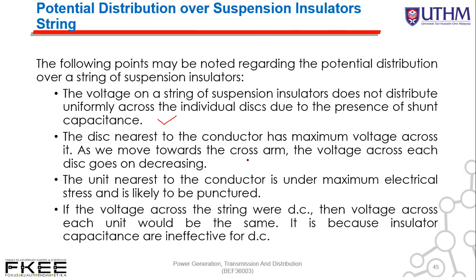As we move toward the cross arm, daripada bawah, kalau katakanlah ni konduktor, kemudian naik ke atas, kita ada 3 disc, C, C dan C. So voltage yang paling bawah, dekat konduktor, paling tinggi, kemudian naik ke atas, voltage dia makin berkurang. Okay, the unit nearest to the conductor is under maximum electrical stress and is likely to be punctured. If the voltage across the string were DC, the voltage across each unit would be the same. Kenapa? Kerana insulating capacitor tidak berfungsi untuk DC.